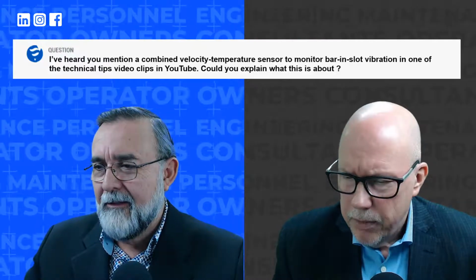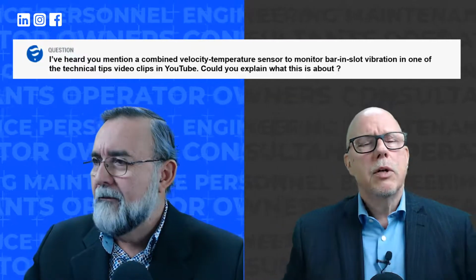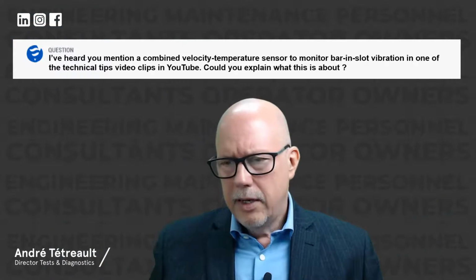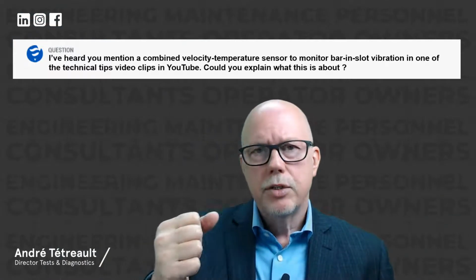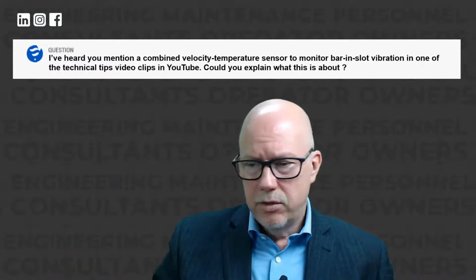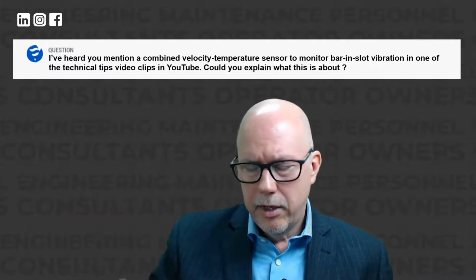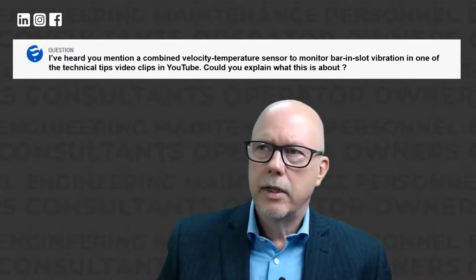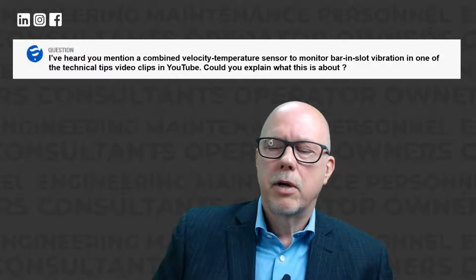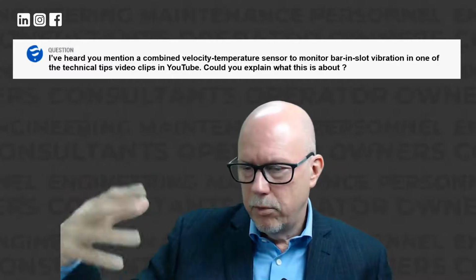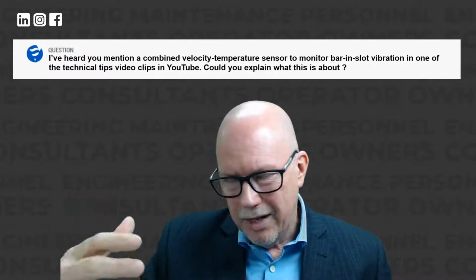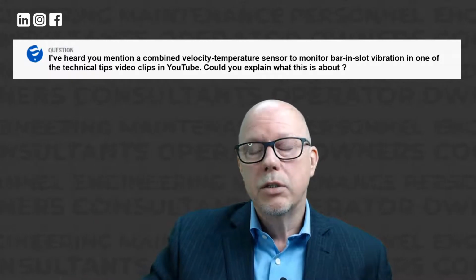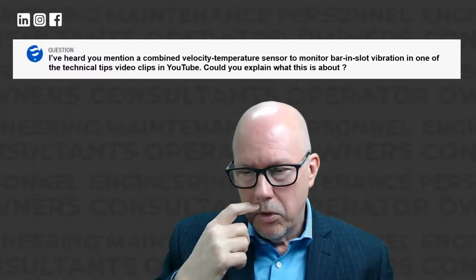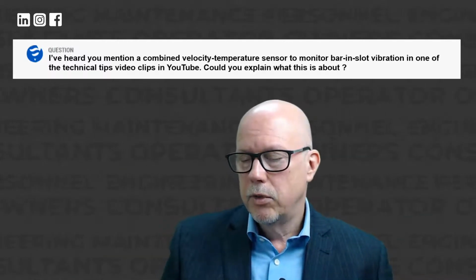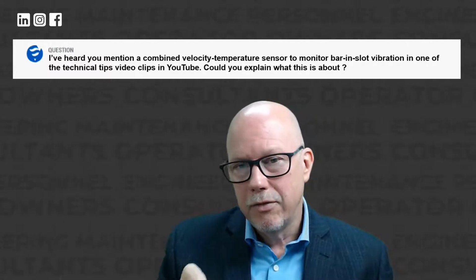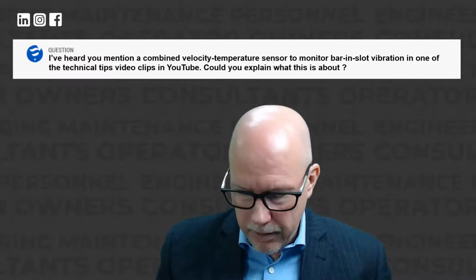Yeah, I did touch upon it a little before. Good question. When looking at end winding vibration, phase leads, phase drops, or the entire electrical circuit, and also stator bar vibration in the slot, we have the fiber optic technology for high voltage locations, and we have capacitive probes that can look at the vibration of the bar inside the slot.